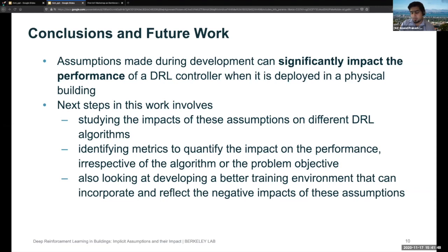Some of the steps we took were, after we had a model, we still did a lot more calibration when we identified issues. When I said our model was calibrated using standard practices, we initially had a normalized mean bias error of less than 10% with the actual system. In spite of this, we saw all these issues pop up. So the only way is to characterize the systems better, identify what control sequences are used, and try to incorporate those control sequences into the modeling as well. That might help deep reinforcement learning understand the performance and behavior of the equipment better—so, better modeling and calibrating basically.